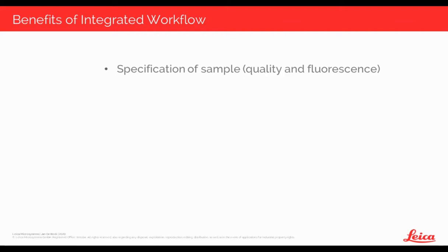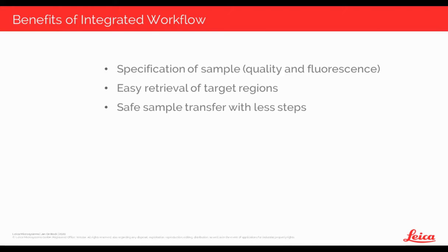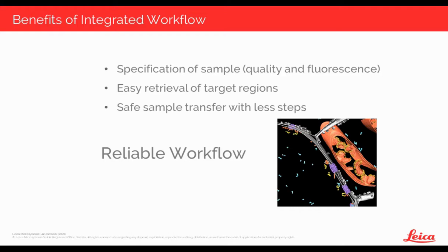The benefits: you can assess sample quality by transmitted light and fluorescence distribution; you can easily retrieve target regions via the software interface between instruments; sample transfer is safer because you have fewer steps and don't need to unclip the auto grids. This provides a more reliable workflow, and the target result is a nicely rendered tomogram.